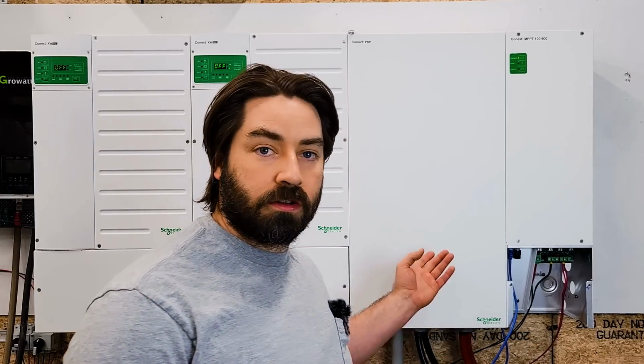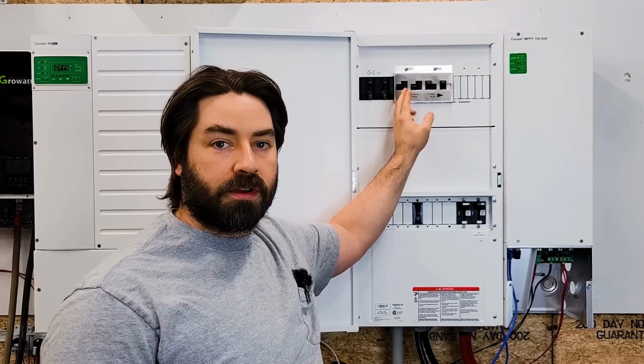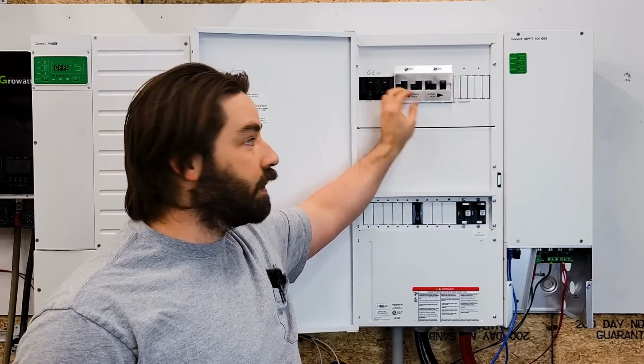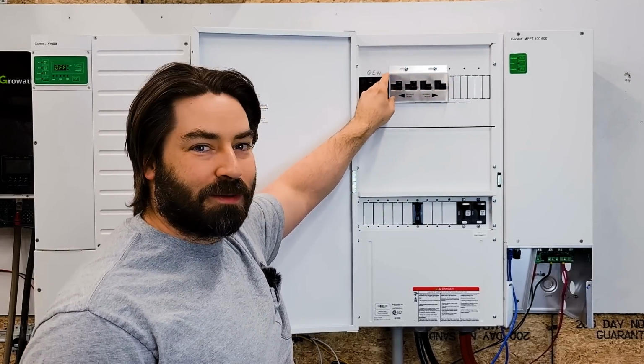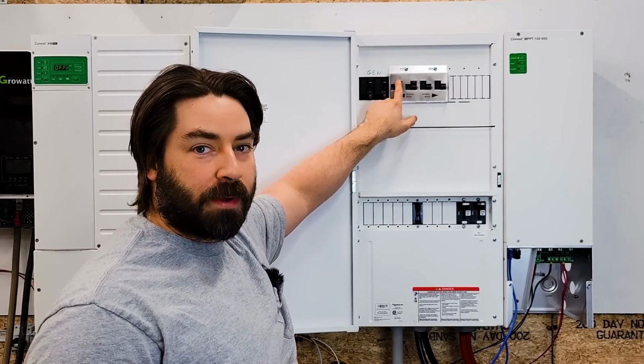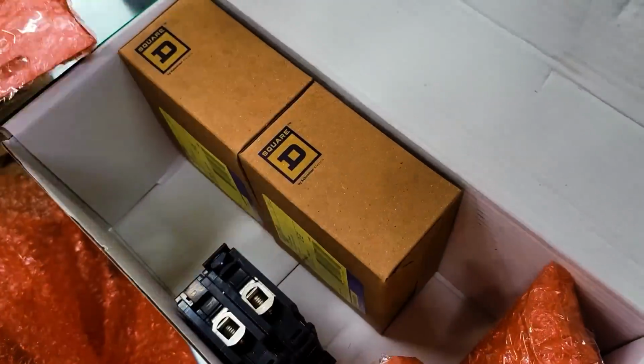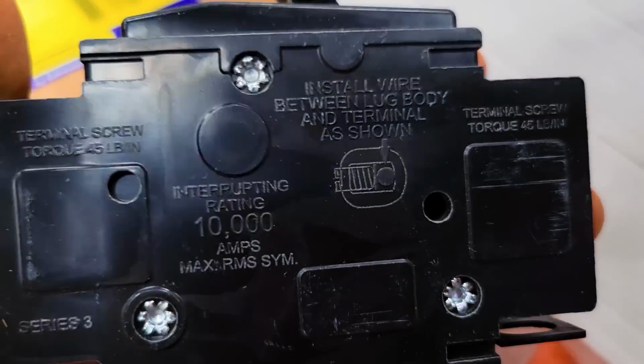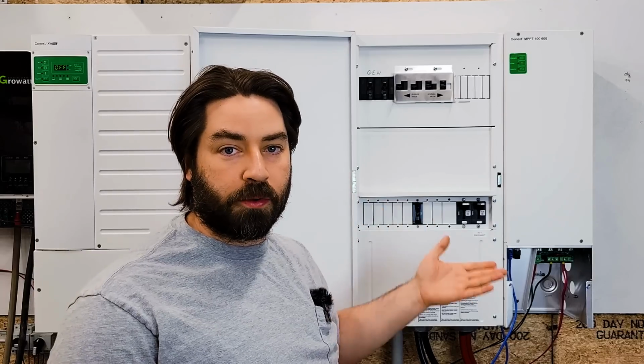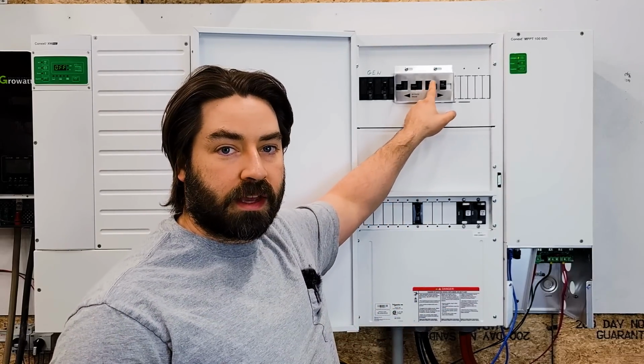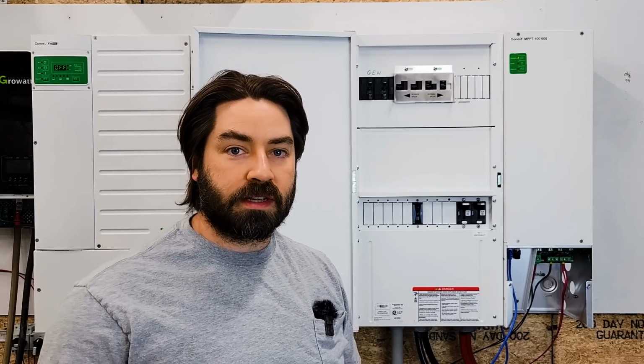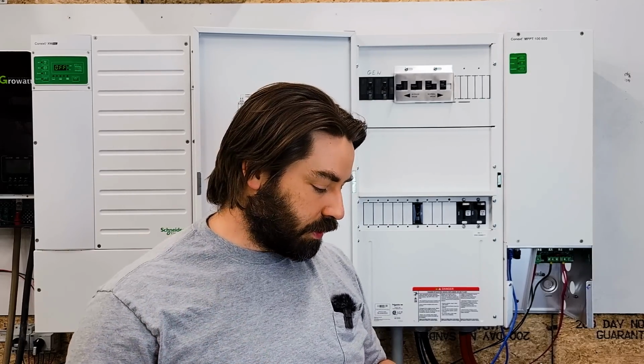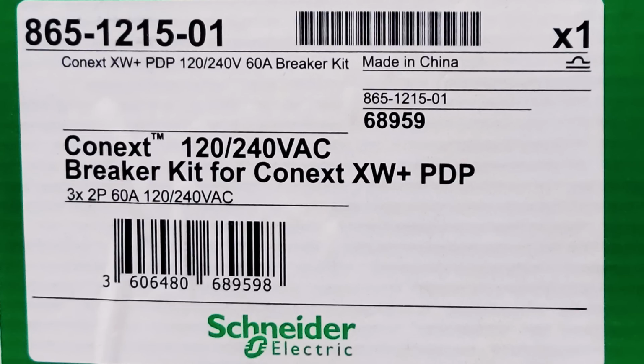In addition to the connection kit, you also have the option of buying some additional circuit breakers. So let me show you the circuit breakers over here. There are additional circuit breakers and this cool plate. If we turn this off, we can slide the plate back and forth, and that allows for bypass mode. So if anything goes wrong with the inverters and you need to wait for a part to get repaired, you can run the grid, or in my case, the generator, directly to your loads by running it in bypass mode. So this bypass plate keeps you from accidentally having both on at the same time. The plate and the extra breakers come in an additional box. It's an extra part number, and that part number is up here on the screen. So that's the extra breaker kit.